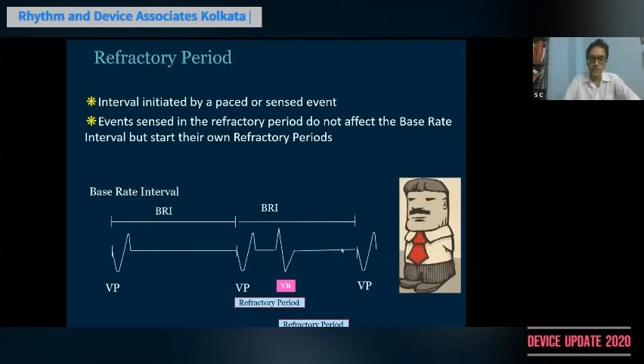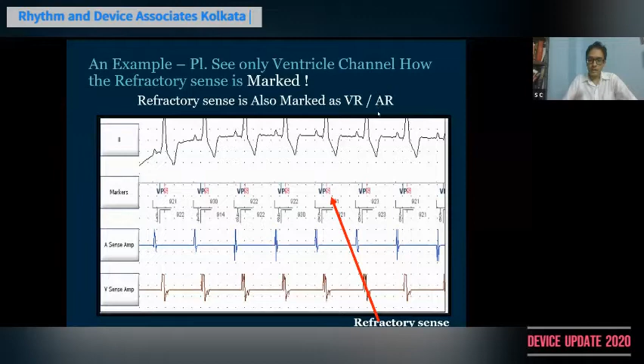So in the same patient with programming of a ventricular refractory period, you now have something being sensed, but that sensing is not leading to resetting the rates because it is falling into the refractory period. That is the concept of your refractory period. Now with constant evolution, something else came up, which is called a blanking period. As you can see in the previous slide, if something falls in the refractory period, it is not resetting your base rate intervals, but it is being recognized. It is definitely being stored by the pacemaker as a VR or an AR event as required.